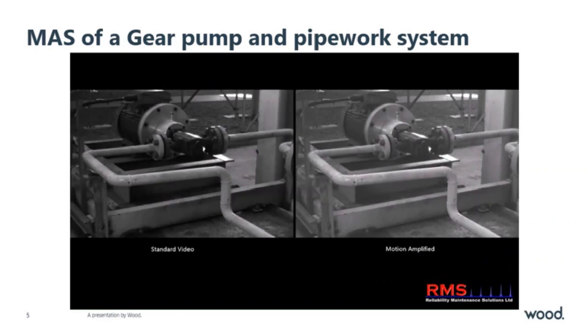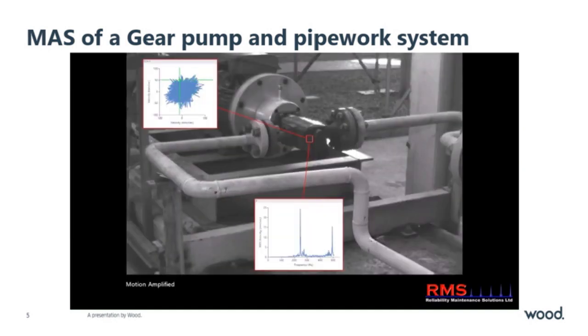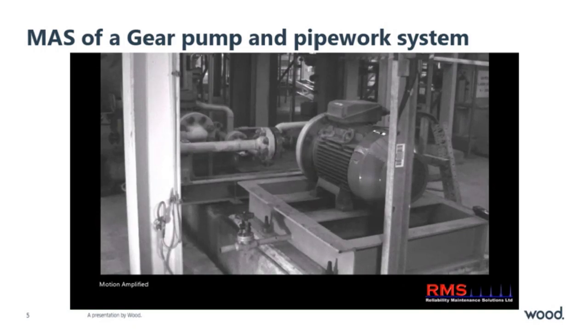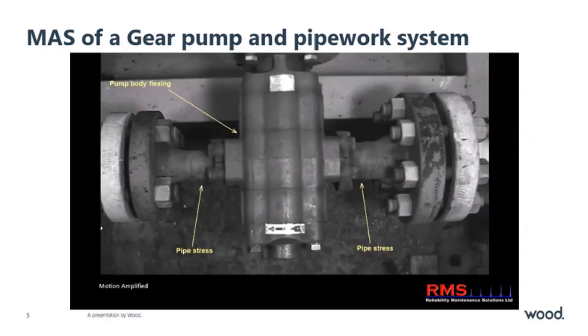Here you can clearly see that the pipework is wobbling, but the concrete isn't. That's because the pipework is moving more considerably than the concrete, but it's also subtle in real life, so your eyes would never really pick it up. So this software is assisting you in visualizing the problem. Now remember, you are getting real data out of it, measurable data. As you can see there, there's accelerations, there's frequency being picked up. I bet you're thinking though, by factoring the video up, you could make anything look terrible. And yes, that's right, you can.